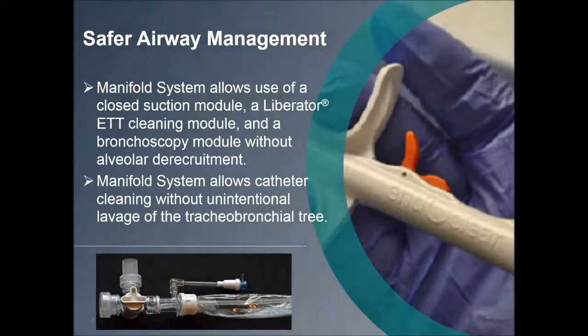As we have now seen from the two demonstrations, the manifold system allows use of a closed suction module, a Liberator ET tube cleaning module, and a bronchoscopy module without alveolar de-recruitment. Additionally, the manifold system allows catheter cleaning without unintentional lavage of the tracheal bronchial tree, because when the stopcock is closed, no saline can be lost into the endotracheal tube and drip into the lungs, carrying with it bacterial and fungal elements.